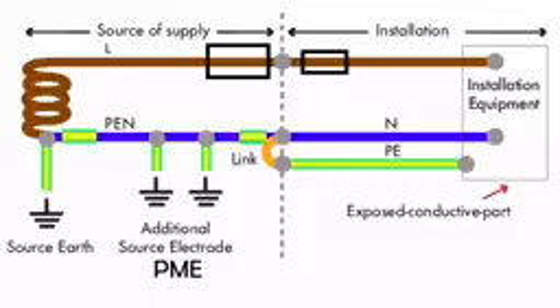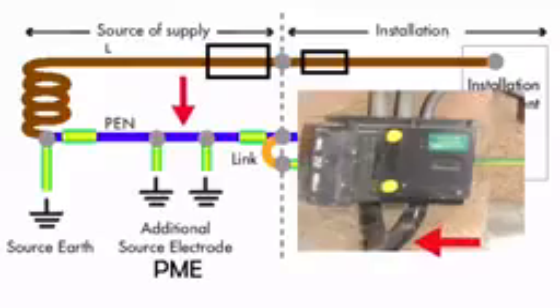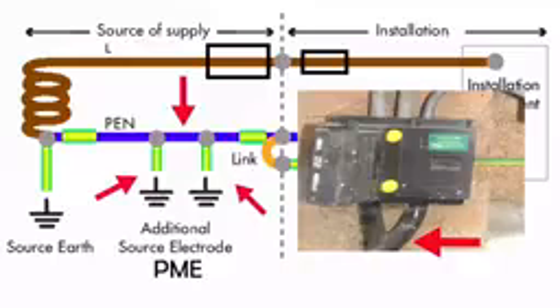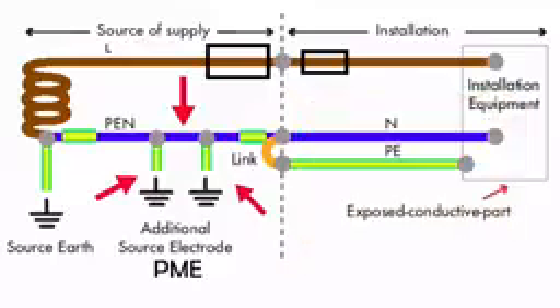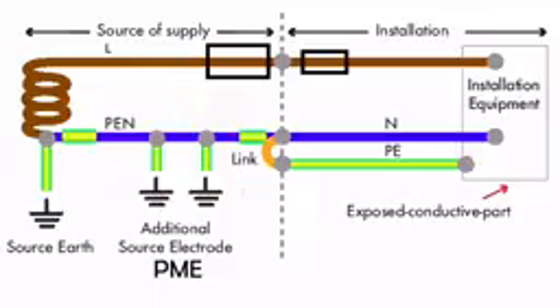neutral. This PEN conductor on the supply authority side is earthed throughout its run. We call this PME, protective multiple earthing. This PME in the PEN conductor is very important, as loss of the neutral on the supply authority side would mean loss of the protective conductor in the installation. PME helps to prevent this happening.